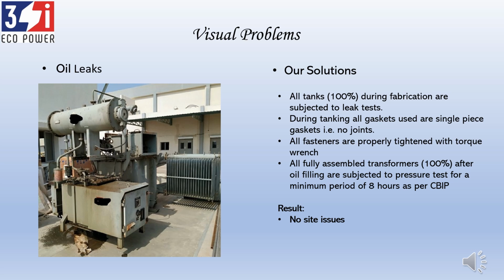Then all fasteners, again 8.8 grade as I said, are properly tightened with a torque wrench and cross-checked. Once we do all these things, even during fabrication of the transformer, we do stud welding for all the pockets, bushings, and radiators. There are no bolts or holes on the tank where you'd mount radiators or anything else.